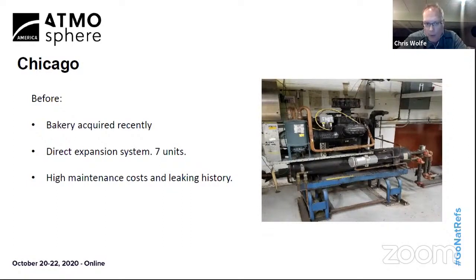This bakery was acquired about 5 years ago. It was one of the last commercial bakeries I'm aware of that still used direct expansion. The good news was they had converted over to 422B, so it was no longer R22, but the bad news is it continued to leak, which isn't good for what we value. We recognized it quickly.